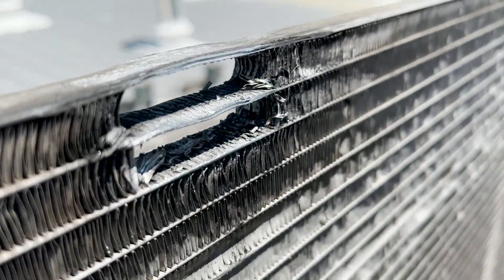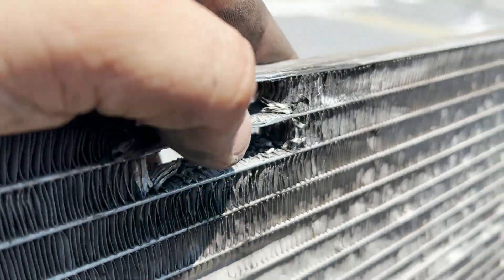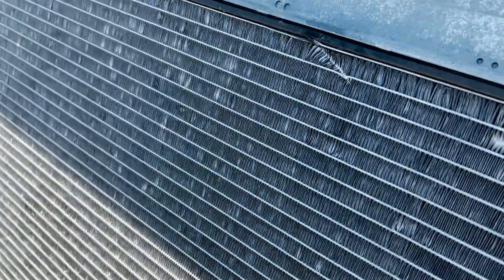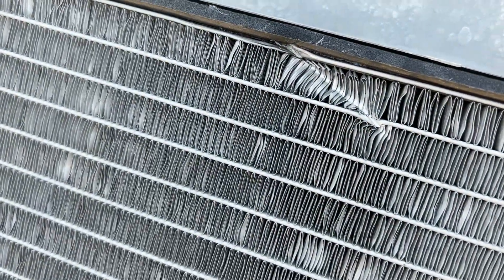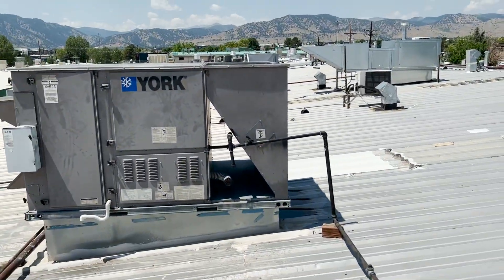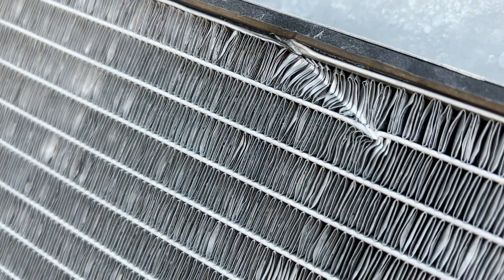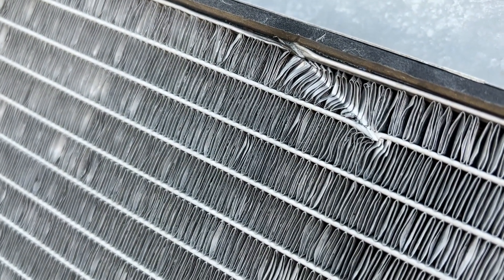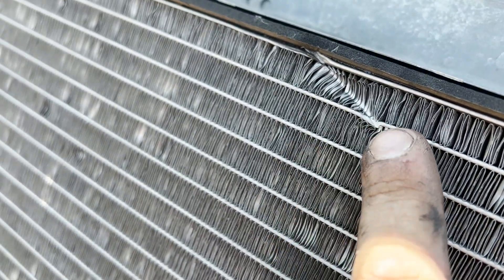We are just getting ready to put this together. There's our big ol' leak right there, and I noticed its sister coil has this fat nick in it. It's not bubbling yet, which is amazing, but I swear that one has the same nick. That's not what we're here for today, but it's worth putting in the notes that if this one leaks, check right here.